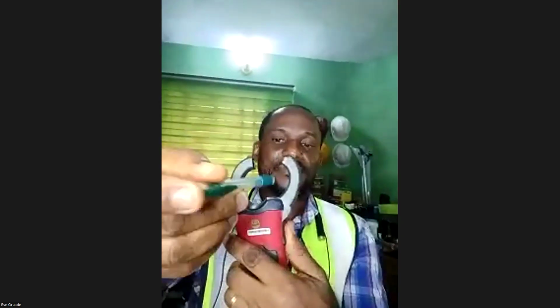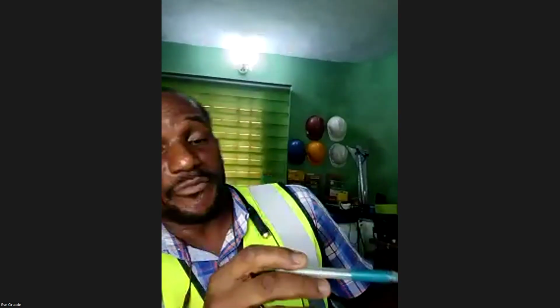If this is your cable, you just insert it, and you must set it to the current range you want to measure. This one has different ranges. The first meter I used has auto range, which selects the range by itself. But this one you have to set manually, from 2 amps, 20 amps, 200 amps, and 400 amps. So if the current you expect to measure is, say, 15 amps, which is larger than 2 amps, you set it to 20 amps, meaning you can measure between 2 and 20 amps at that position.